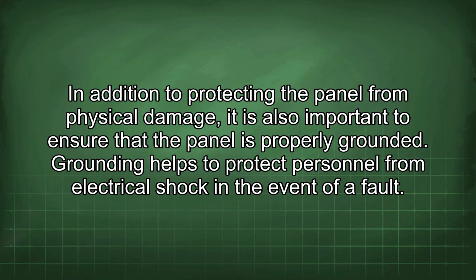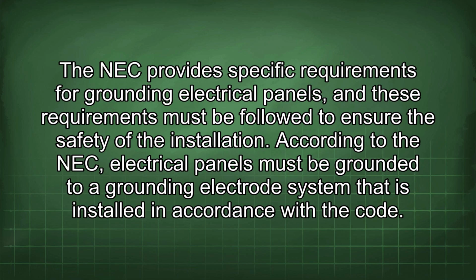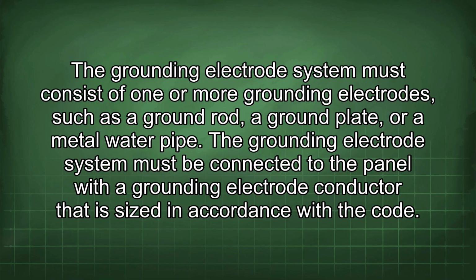In addition to protecting the panel from physical damage, it is also important to ensure that the panel is properly grounded. Grounding helps to protect personnel from electrical shock in the event of a fault. The NEC provides specific requirements for grounding electrical panels, and these requirements must be followed to ensure the safety of the installation. According to the NEC, electrical panels must be grounded to a grounding electrode system that is installed in accordance with the code. The grounding electrode system must consist of one or more grounding electrodes, such as a ground rod, a ground plate, or a metal water pipe.